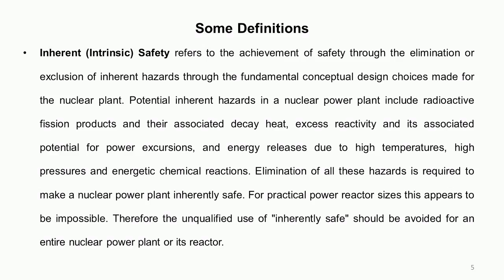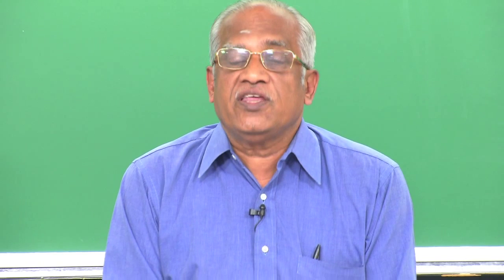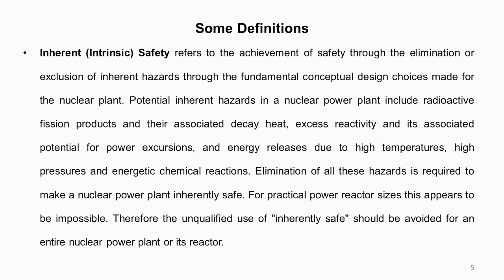The hazards in a nuclear power plant include: fuel failure, radioactive fission products coming out, decay heat needing to be removed, and if the reactor is not shut down or decay heat is not removed, there could be fuel melting, energy releases, and high pressures generated due to the reaction of hot fuel with the coolant. In a practical way, it is not possible to take care of every step. So very carefully, when we say the word 'inherently safe', you cannot say a reactor is inherently safe — for some events maybe it is intrinsically safe.